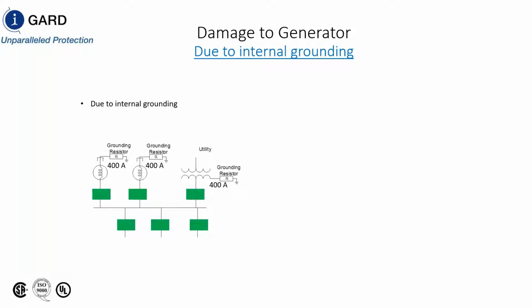Now we're going to take a look at what we do as protection engineers. So you still have the same stator fault winding. You open up the breaker in 100 milliseconds. But what we haven't shown here is we haven't really cleared this fault. We did what we could as protection engineers, and we opened up the breaker, separating the load from the generator, but we haven't separated the ground fault from the stator winding because it's still captured inside this area.